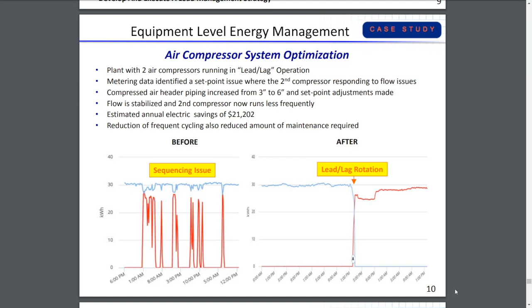So we made some changes to piping, we adjusted set points, and we were able to get that system to the point where, as shown on the chart on the right, only one unit was running. And you see a switch halfway through that chart because since only one unit's running, they decided to rotate and share the work between the two. But the overall savings were a reduction in kilowatt hours, a reduction in peak, a reduction in units starting and stopping, which can be a maintenance issue. So there are a lot of different revenue streams for savings. And it started as just monitoring the unit for cost, but by looking at the data and drilling down, there were a few other opportunities.